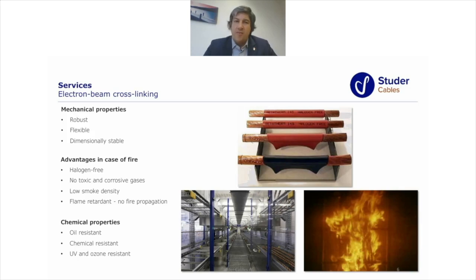aging failures happening with the cable. On the other hand, if you apply electron beam cross-linking, you are affecting the polymeric structure for a specified time, at a specified strength and performance. Once the process is done, it's finished, and the elasticity or physical properties of the cable will remain unchanged for the whole lifetime of the installation.